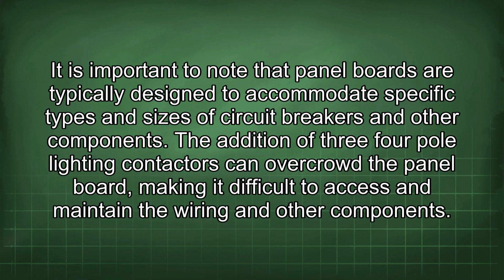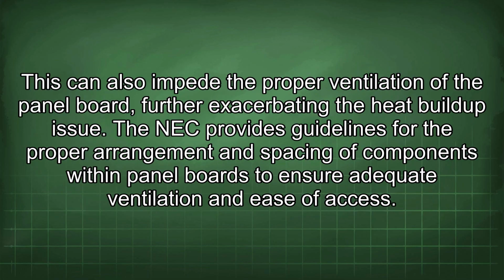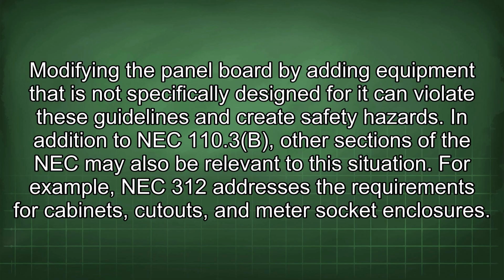It is important to note that panel boards are typically designed to accommodate specific types and sizes of circuit breakers and other components. The addition of three four-pole lighting contactors can overcrowd the panel board, making it difficult to access and maintain the wiring and other components. This can also impede the proper ventilation of the panel board, further exacerbating the heat buildup issue. The NEC provides guidelines for the proper arrangement and spacing of components within panel boards to ensure adequate ventilation and ease of access. Modifying the panel board by adding equipment that is not specifically designed for it can violate these guidelines and create safety hazards.